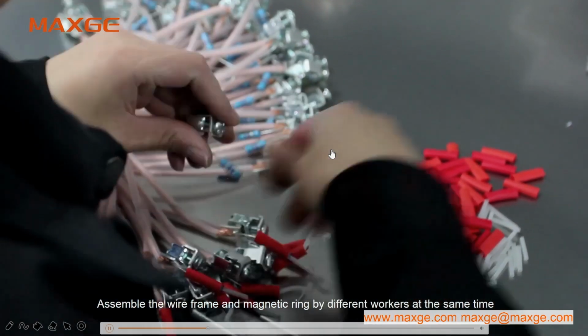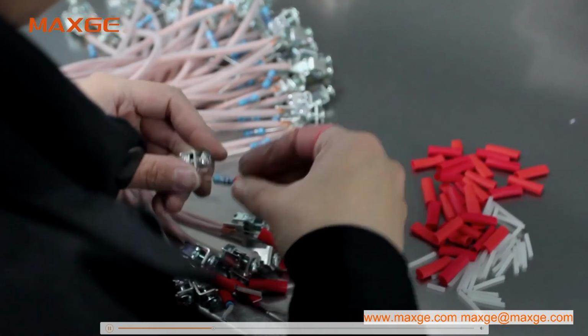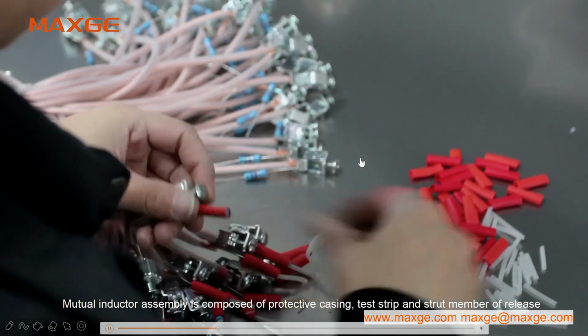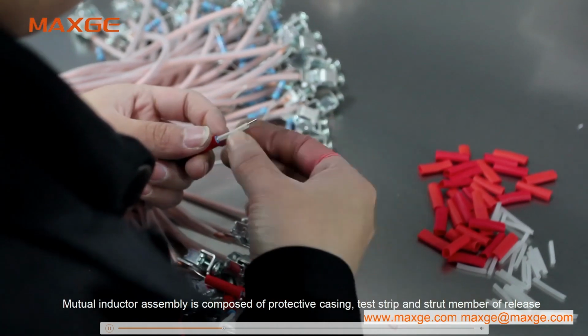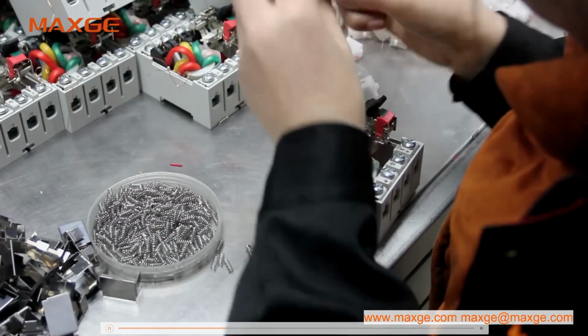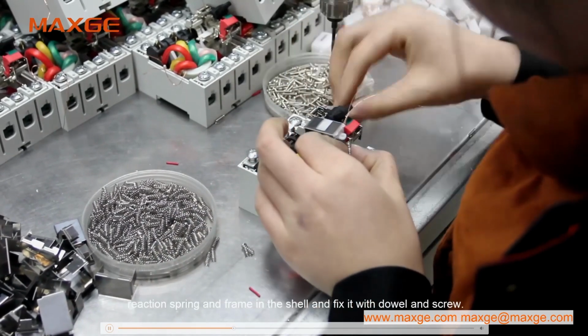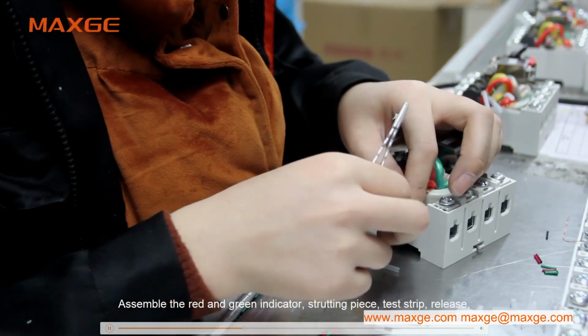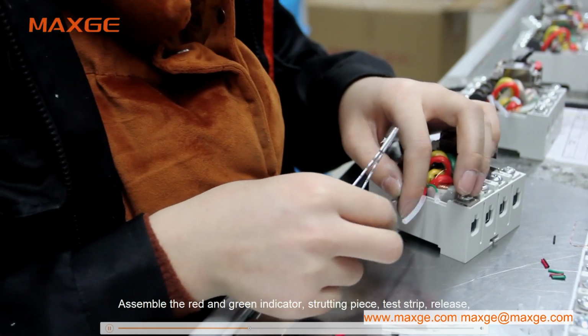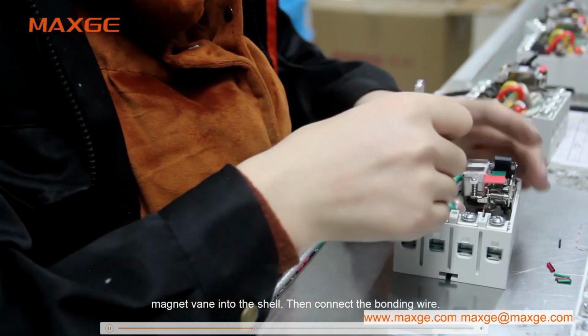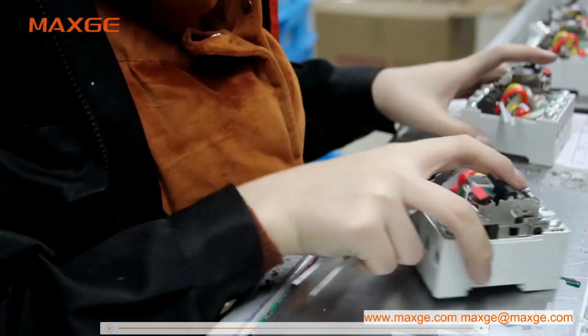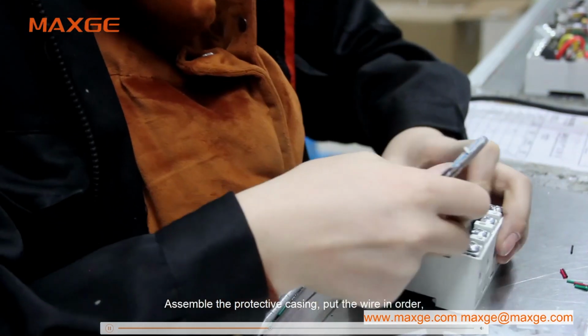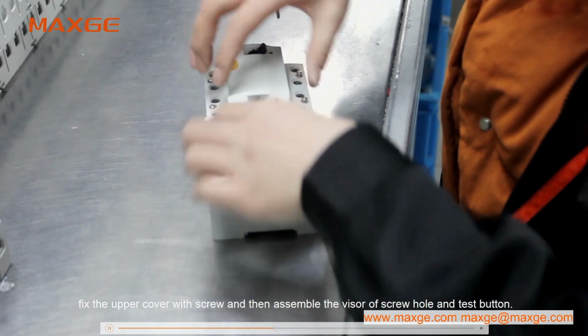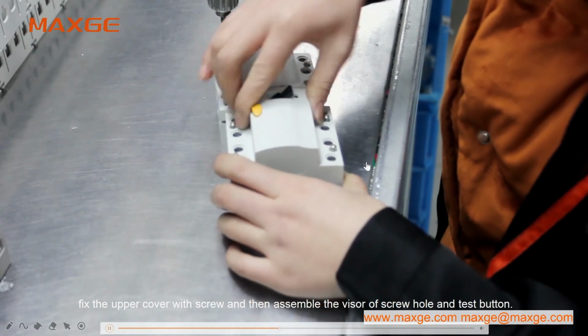Assemble the wire frame and magnetic ring by different workers at the same time. Mutual inductor assembly is composed of protective casing, test strip, and strut member of release. Put the mutual inductor assembly, reaction spring, and frame in the shell and fix it with dowel and screw. Assemble the red and green indicator, strutting piece, test strip, release, magnet vane into the shell, then connect the bonding wire. Assemble the protective casing, put the wire in order, fix the upper cover with screw, and then assemble the visor of screw hole and test button.